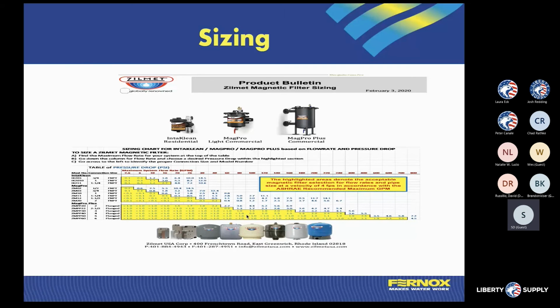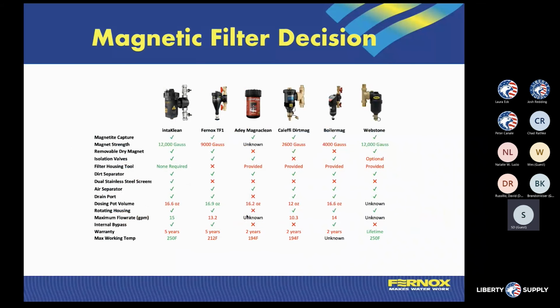You can look at those pressure drop charts that we looked at earlier and try to calculate it, so we made a simple selection chart. Anything in yellow is going to be an acceptable range for those different types of filters. And when you're looking at different brands, the one thing you want to look at is that Gauss rating, connection, how easy it is to remove from the system, how flexible it is on piping. All of those different things are factors, but not all are equal. There's not one size that fits all across the brands, so you need to look at that carefully when you're selecting the brand, the style, and the make of that system. There's a bunch of different brands out there, and we can walk you through the process of selecting the right one.